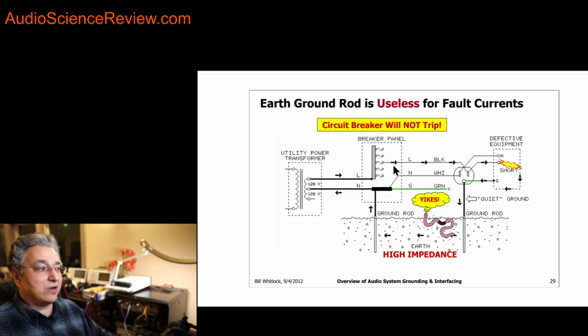Now let's follow what happens when we have this same short. The hot wire comes in here, connects to the chassis, connects to the ground, goes to the ground wire, but it can't follow this path anymore because that's disconnected. Where does the electricity now go? To this new ground rod that he has installed, and it now wants to complete the circuit. So where is the circuit that exists between these two ground rods, right? One is on this side of the house, the other one's on the other side of the house, maybe 50 feet away. You think dirt and vegetation and rocks are great conductors of electricity? They are not. The impedance in here could be 10 or 20, 30, 100 ohms. I mean, it depends on the condition of your soil.